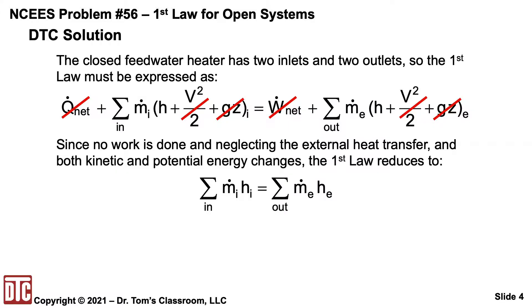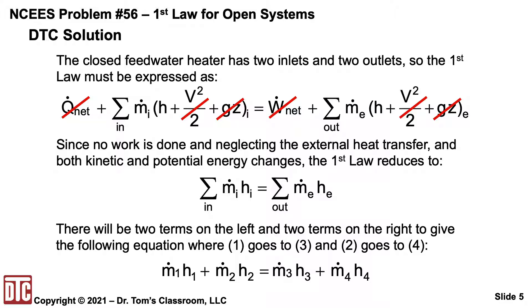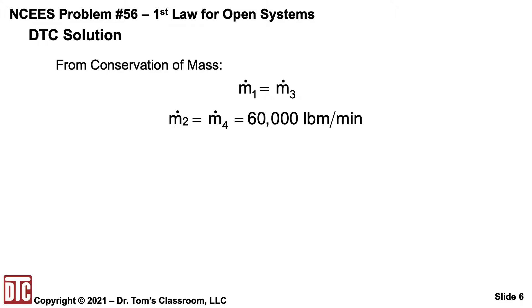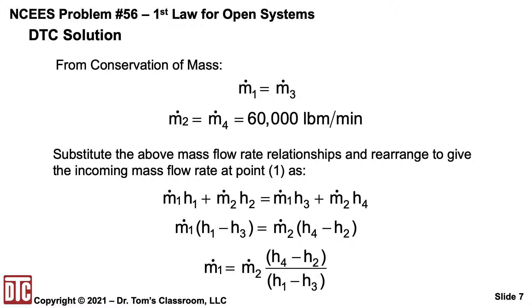We have two in and two out. As denoted in the figure, M1-dot times H1 plus M2-dot times H2 equals M3-dot times H3 plus M4-dot times H4. From conservation of mass, M1-dot equals M3-dot, and we're given that M2-dot and M4-dot are 60,000 pounds per minute. We can substitute those mass flow rate equations and rearrange — expanding terms, collecting terms in M1-dot and M2-dot — and then solve for M1-dot, giving M2-dot times the ratio of two differences in the enthalpies H1, H2, H3, and H4.